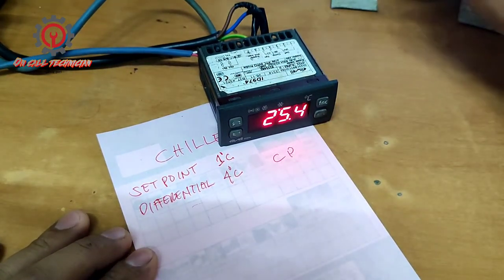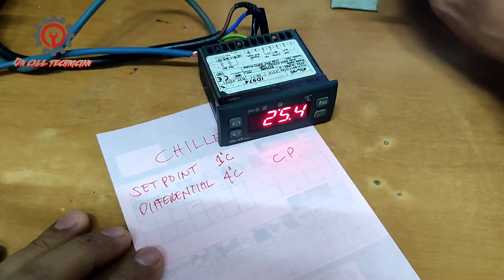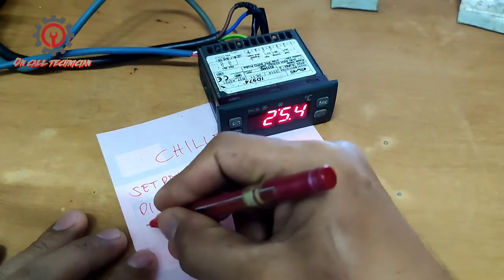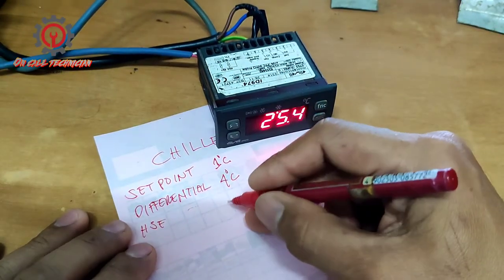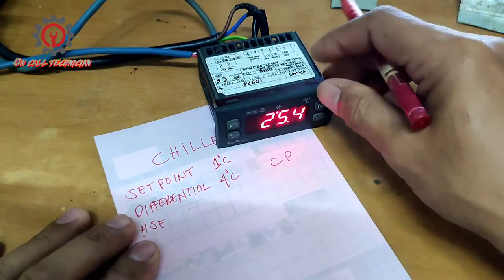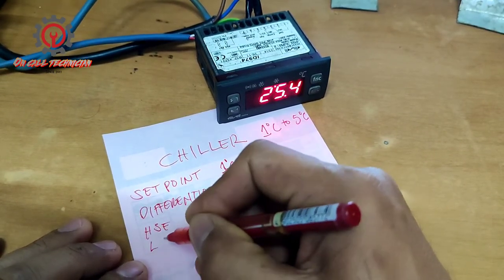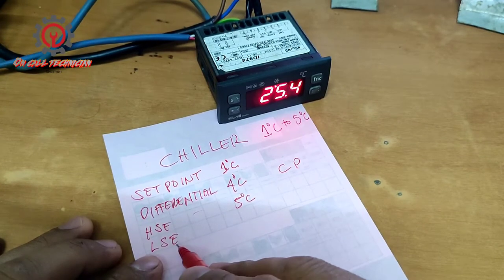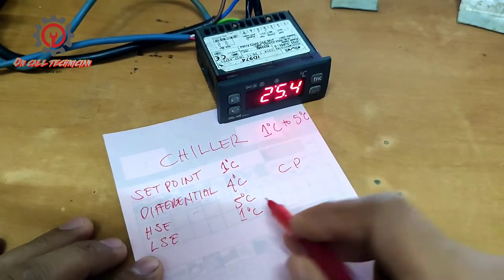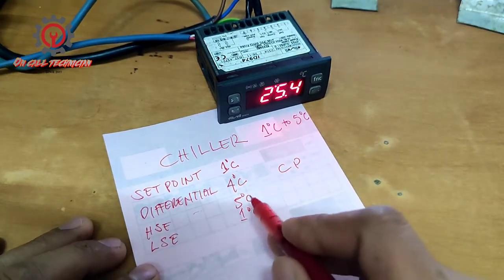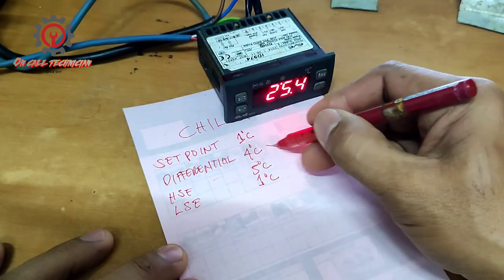If you wish to change the HSE, which is the highest set point, I'm going to set the highest set point to five degrees Celsius. We also have the LSE, which stands for lowest set point, and my lowest set point is one degree Celsius. These two are also under the CP folder, and it's up to you whether you want to set these values.